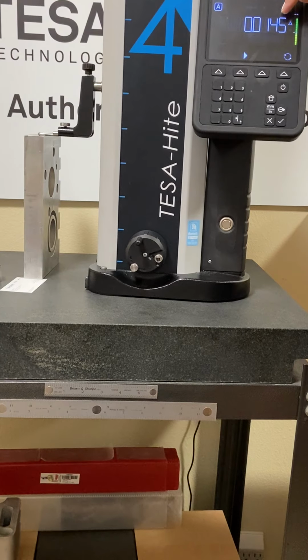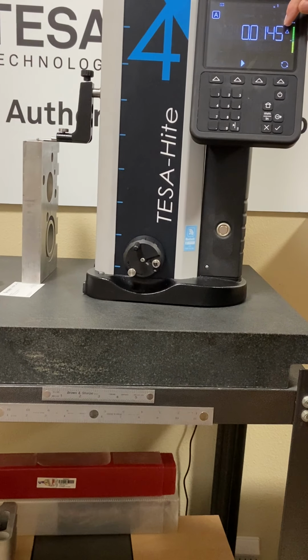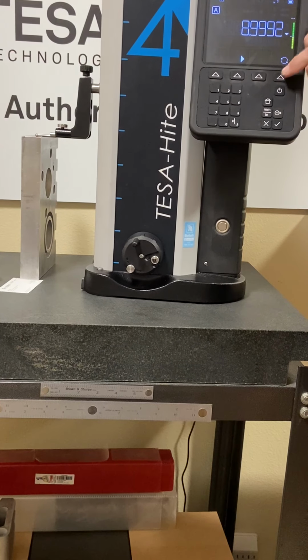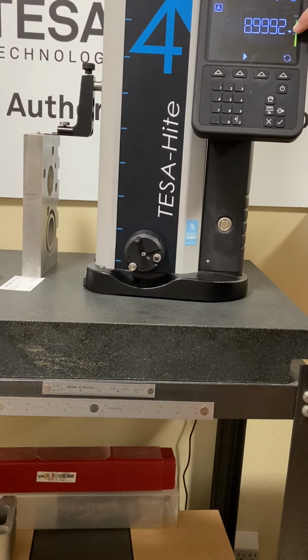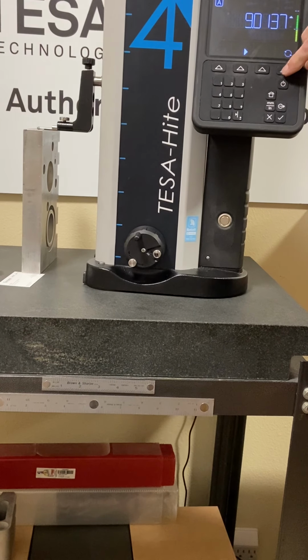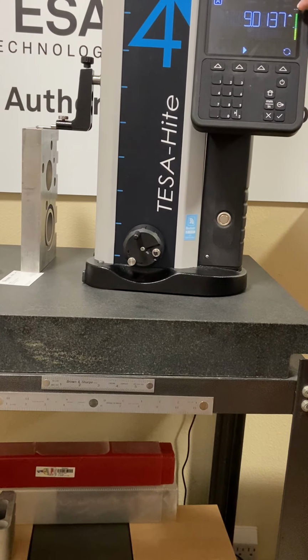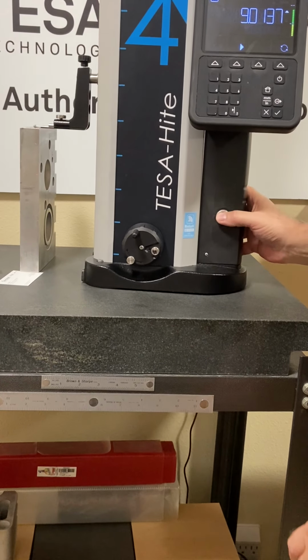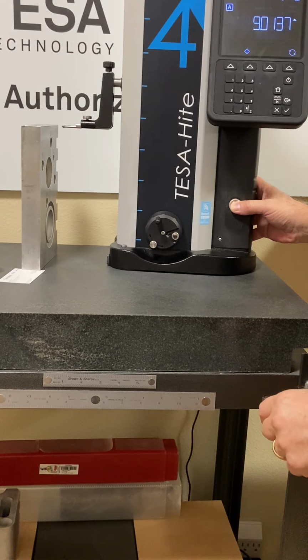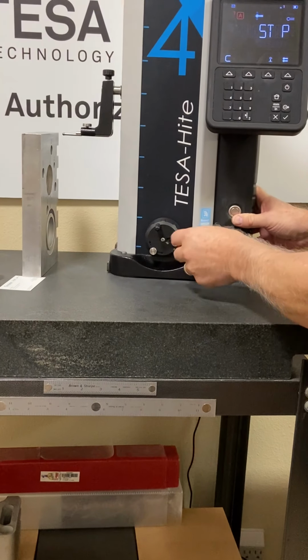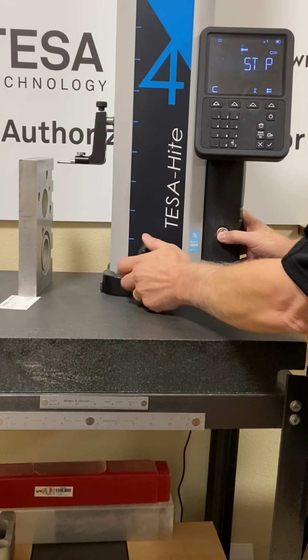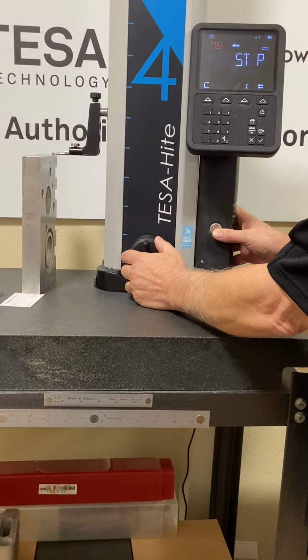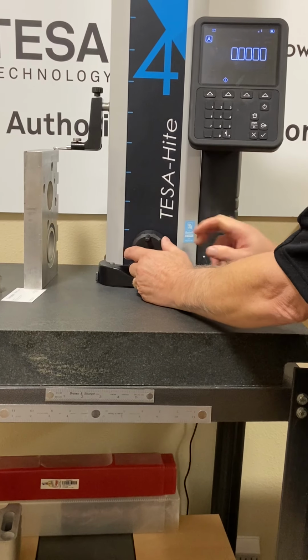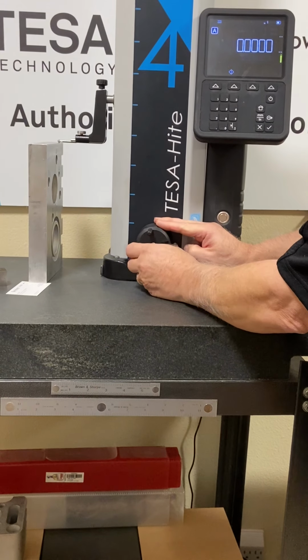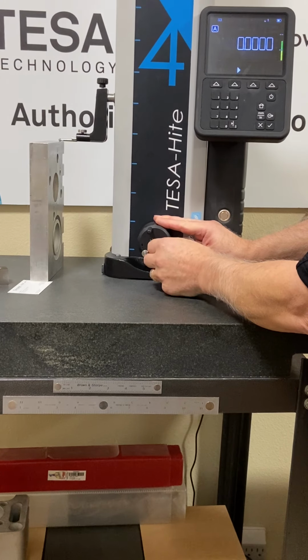And this is telling me the total deviation in reference to the surface plate. If I hit that again, that tells me the low amount or the negative amount. And there, that tells me the positive amount. And again, that's absolute measurement. If I want to see differential, I can go back in here to the main menu. I unlock my probe. And this time I'm going to establish the top of my part that I'm measuring as my datum point. So again, I come down here, I put pressure on it.